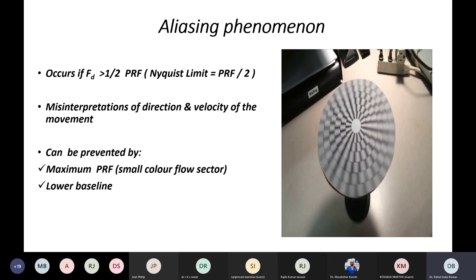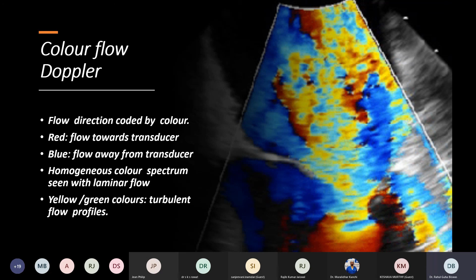Coming to color flow Doppler, color flow Doppler is essentially a derived application. We basically put color based on direction and velocity of RBCs, which is already measured by pulse wave and continuous wave Doppler. It is called BART, as in Bart Simpson. So blue is away from the transducer and red is towards the transducer. Any RBC moving towards the transducer, which we can see and calculate from the Doppler equation, will be given a color of red, and any RBC moving away from the transducer will be given a color of blue. Now again, on the velocity color scale, the higher velocities will be given green, yellow and such colors, so that we can understand areas of turbulence and very high velocities in a particular area. So that is color Doppler.